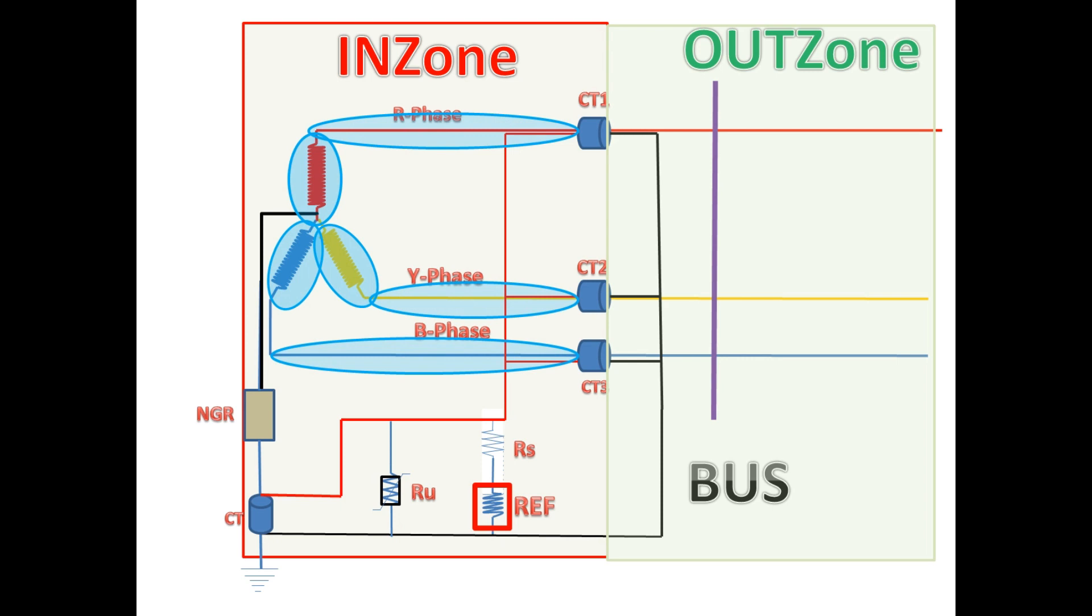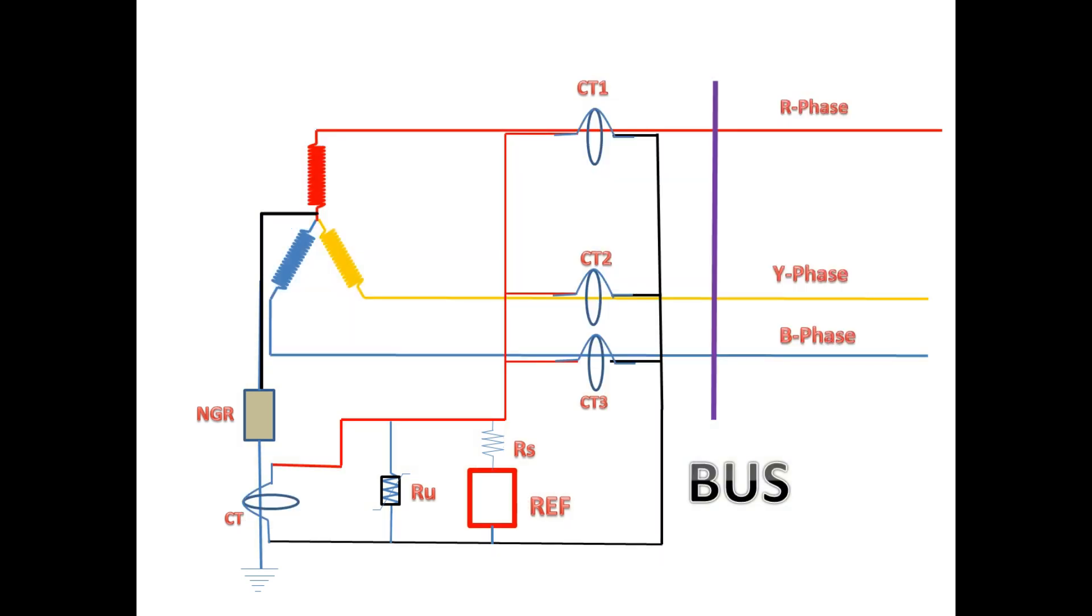Now let's see the REF circuit. In the REF circuit we have one REF relay and two resistors. One is a nonlinear resistor and the other is a linear resistor. The linear resistor is also known as the stabilizing resistor, normally denoted by RS. We will see more about these two resistors in the next video.